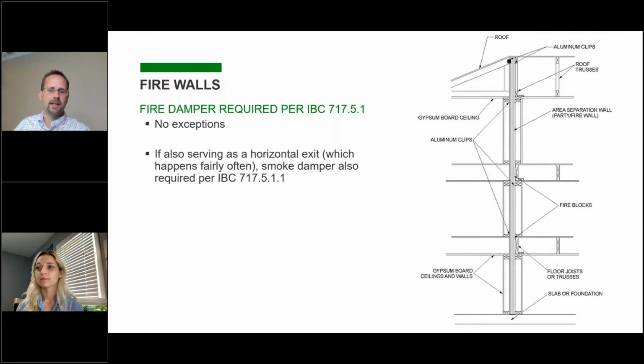But to echo what Glynis was saying, verbiage is really important, and coordination between the code consultant and the design team is really important to make sure the correct terminology is used and we understand what the terminology is actually referring to from a code standpoint, so we don't misapply our codes and add dampers and over design a space for an owner. An important thing to look at, if you see a rated wall that's surrounding just one individual room, it's not a firewall. And so unless it cuts through the entire building, it's most likely some verbiage that needs to be coordinated with the design team to make sure that everybody's on the same page.